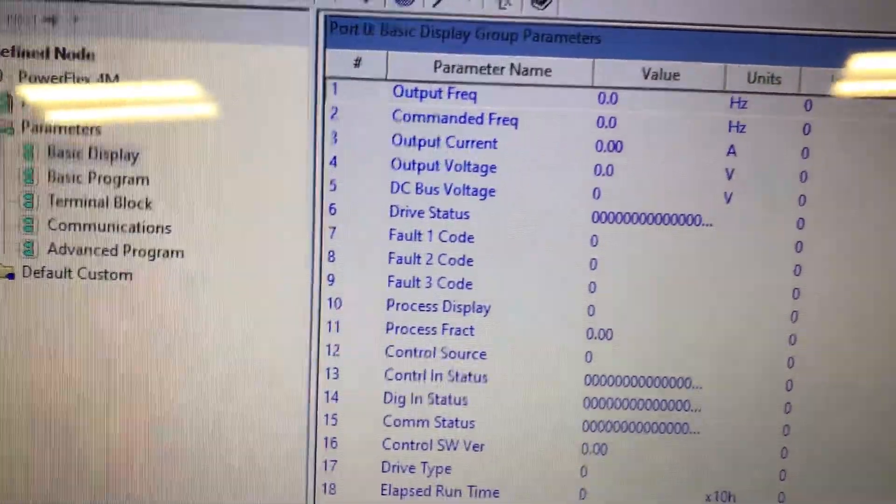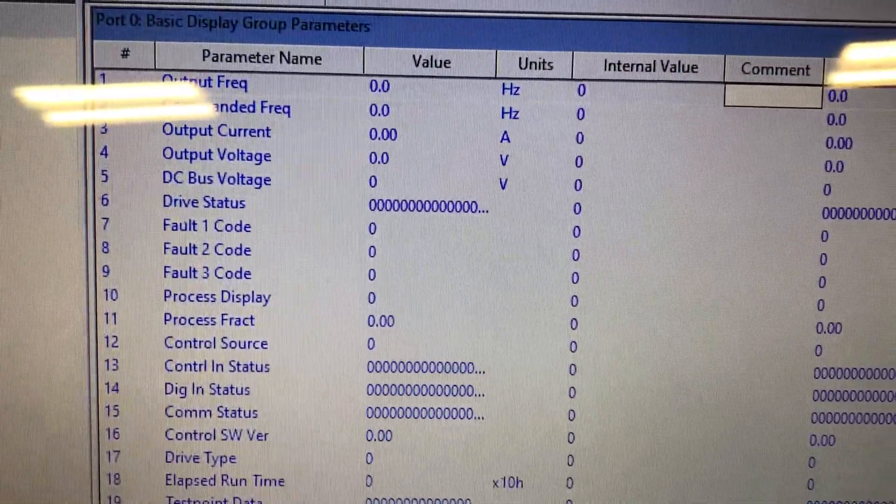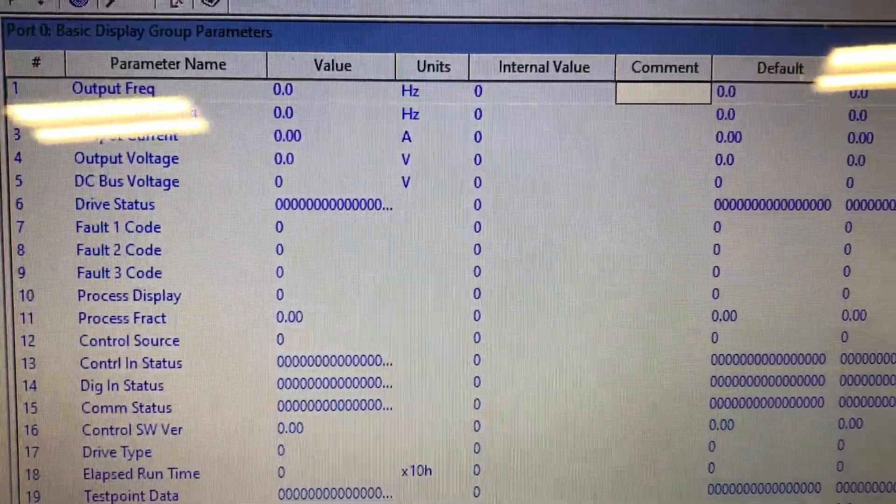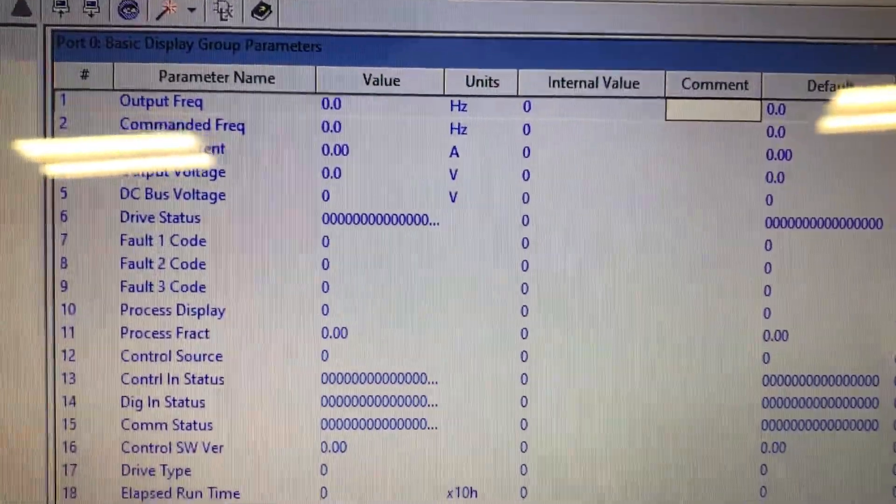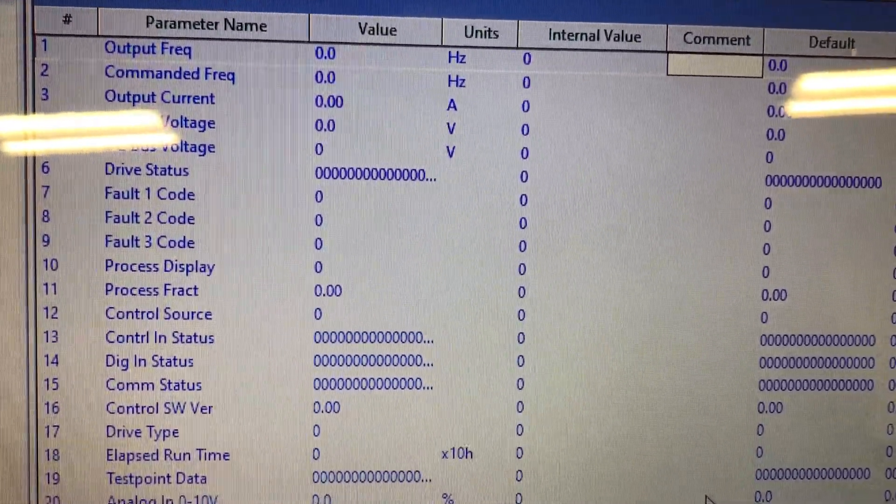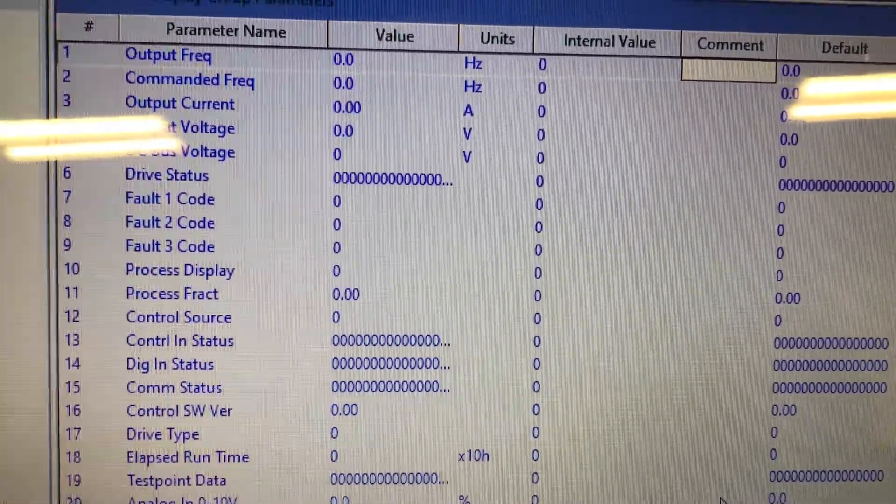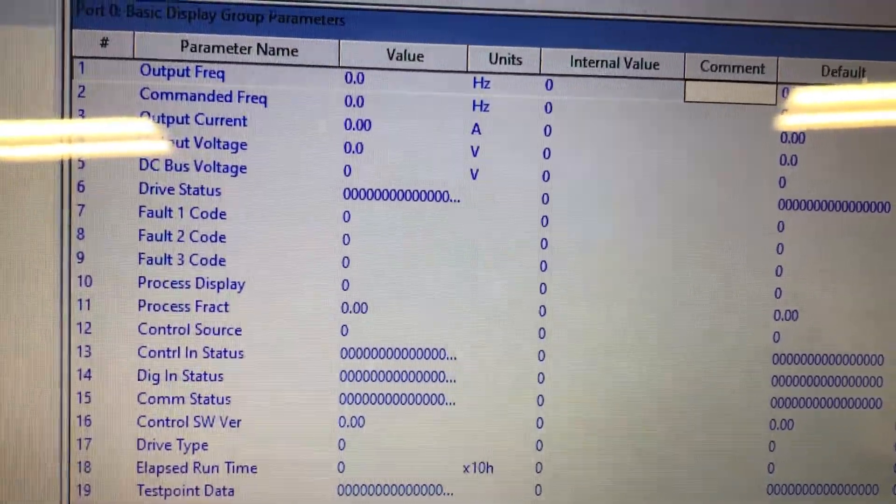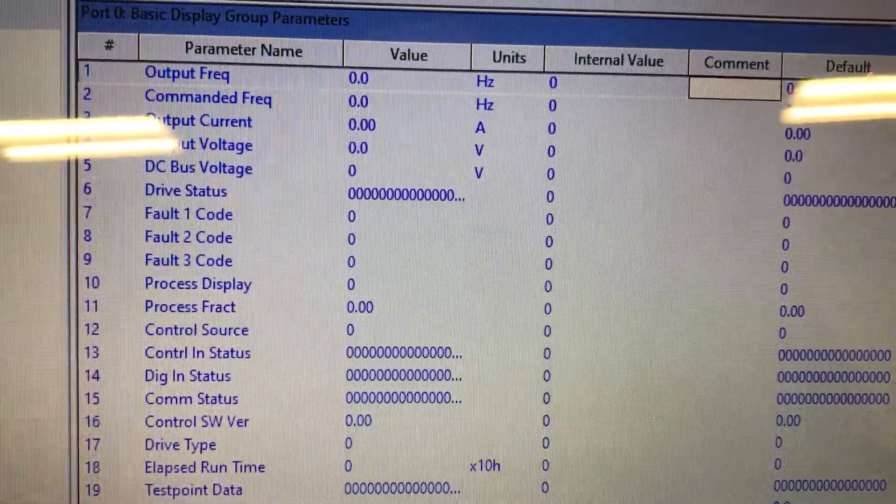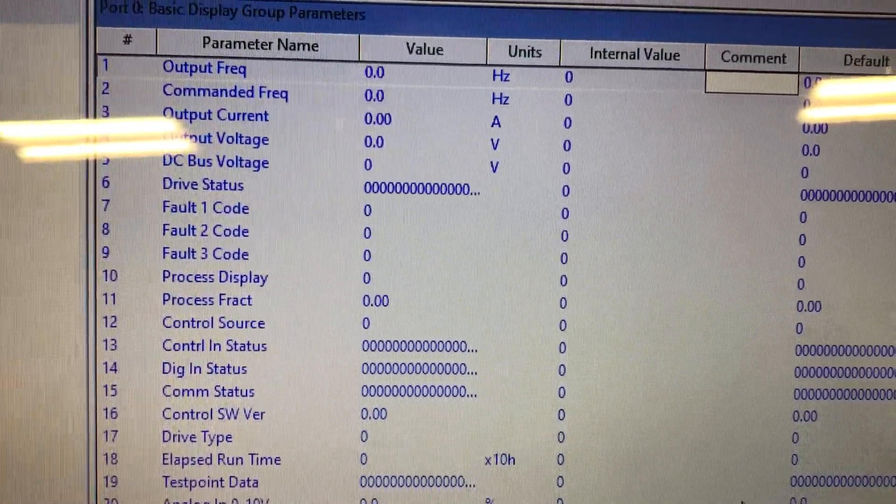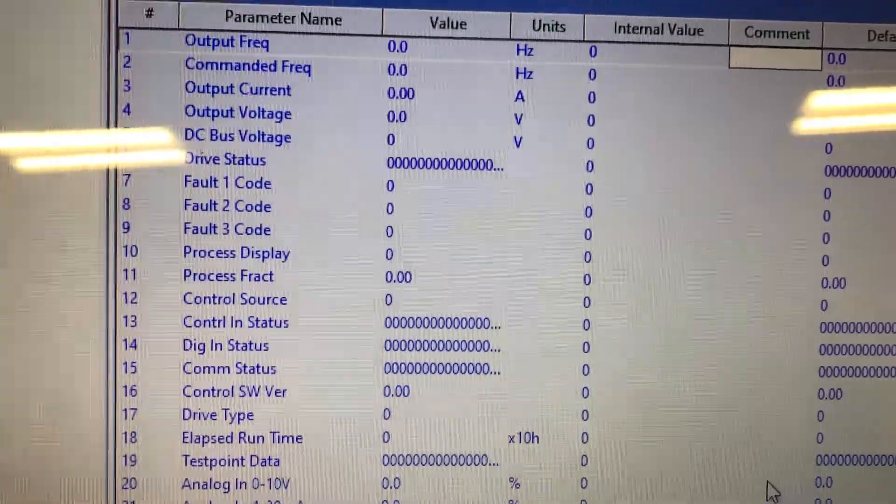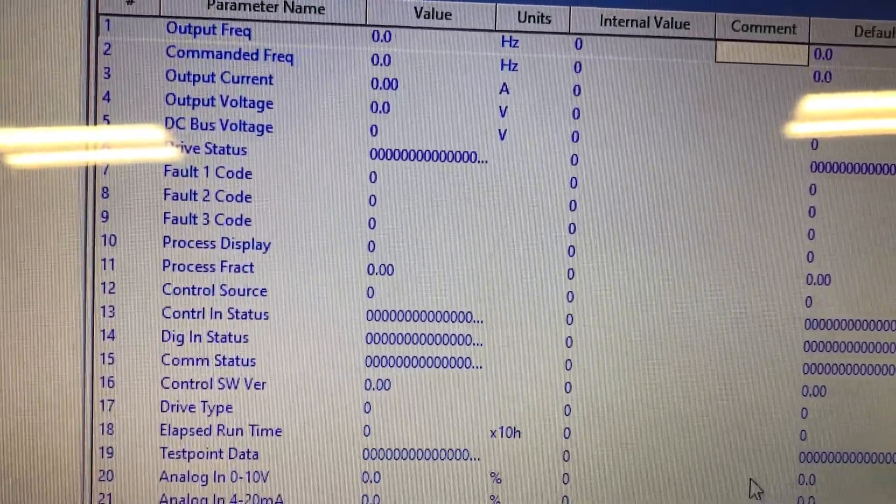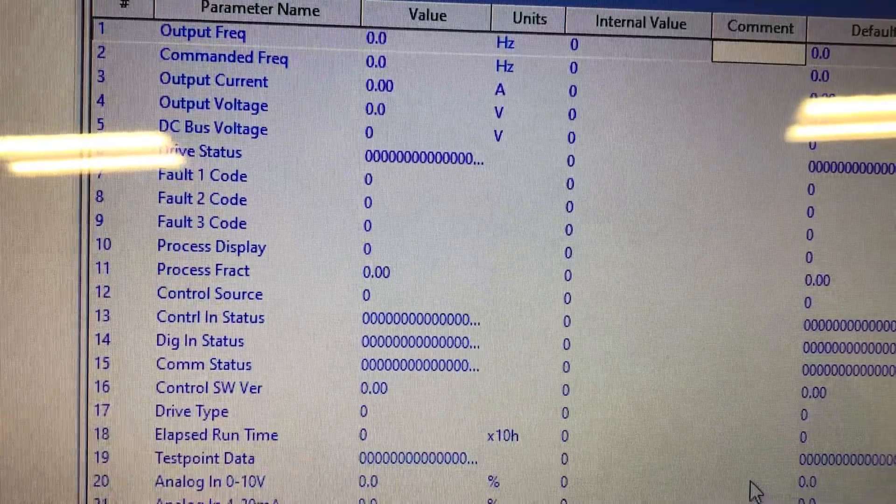So here's the parameter names and the values that they have. The default values, commanded frequency, that's how fast it's going. Output frequency, that's the actual frequency going to the motor that will turn into RPMs. Output current, voltage, there you see our DC bus that I spoke about later.